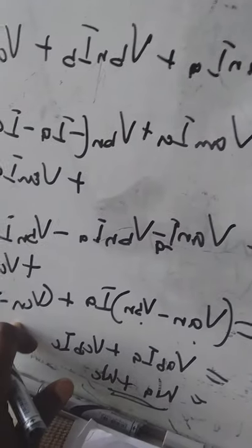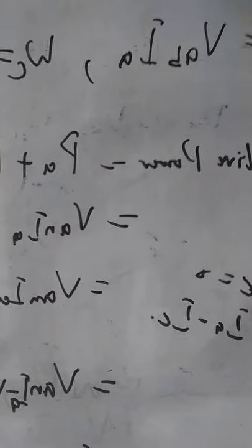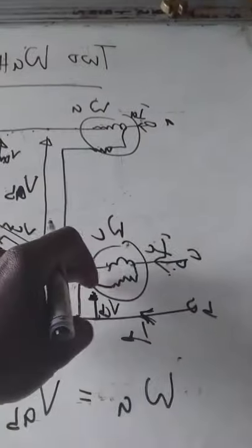So now with this, you use the same system: VCN minus VBN will be VCB, which is this. So VAB IA - that's watt meter reading A, which is WA. VCB IC - that's watt meter reading C, which is WC.